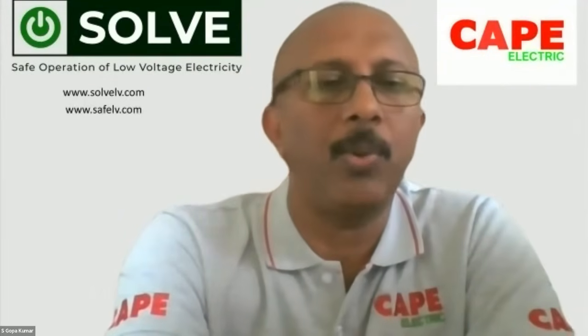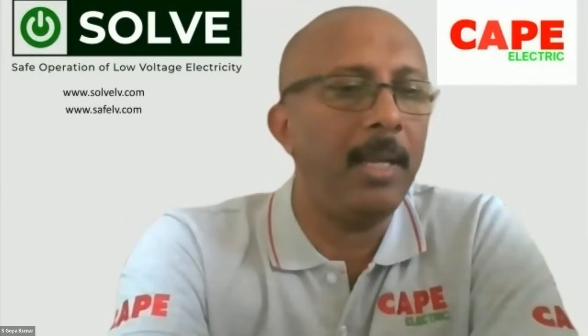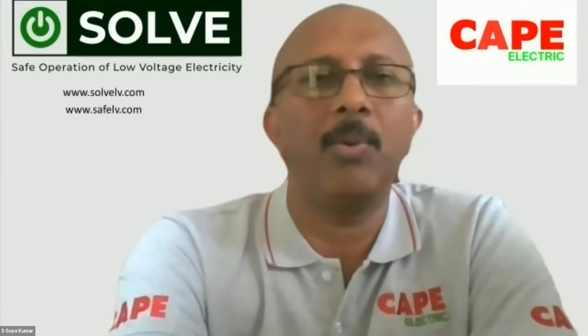With respect to safety, the only written rule is, for example, in the neutral: if the neutral current is more than a certain limit, you can increase the size of the neutral conductor to a certain limit. Still, if the current is more, you are supposed to measure the neutral current and disconnect the phase conductors. Very simple. So measure and disconnect. This means you are not supposed to run a dirty electrical system. Dirty in the sense of a lot of harmonics, more than a certain limit.